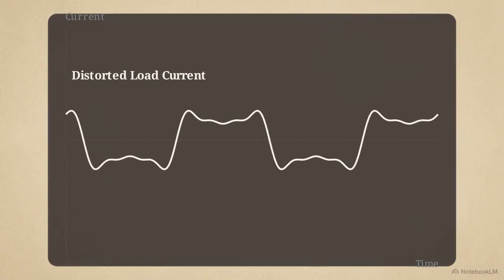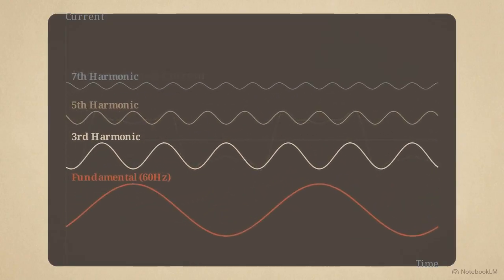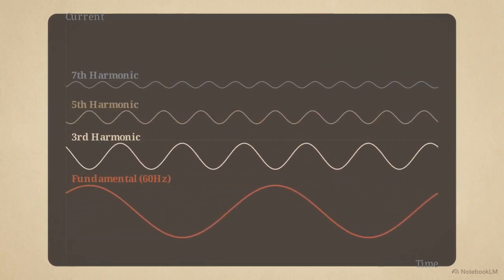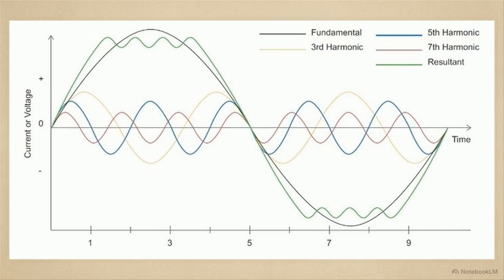current. To decode the damage caused by these jagged waveforms, electrical engineers rely on a mathematical tool called Fourier analysis. The math proves that a distorted wave is actually a stack of multiple higher-frequency pure sine waves riding on top of the base pulse. This chart isolates those frequencies. You see the fundamental wave alongside the third, fifth, and seventh harmonics, unwanted frequencies injected backward into the grid. Summed together, they form the green resultant wave, representing the actual polluted current now flowing.